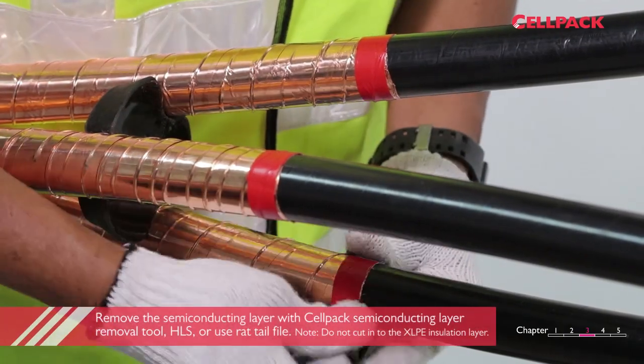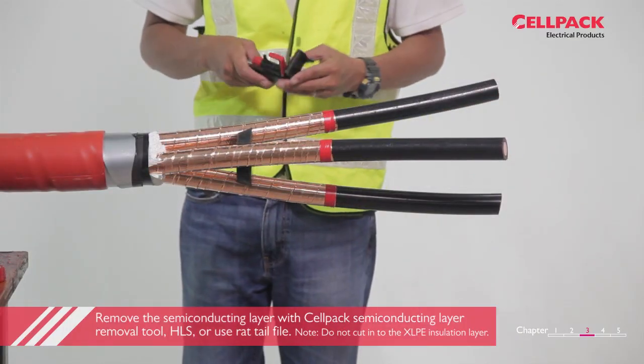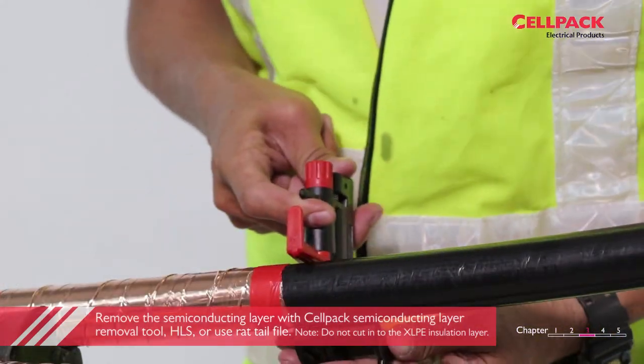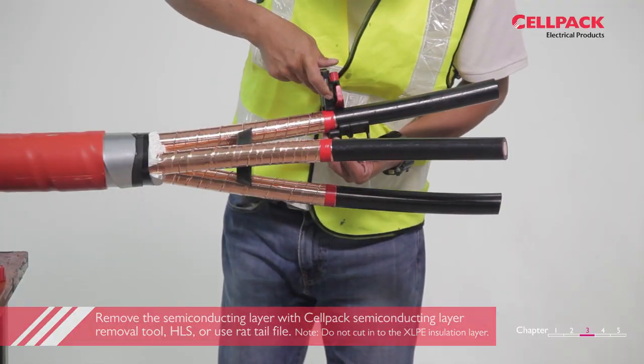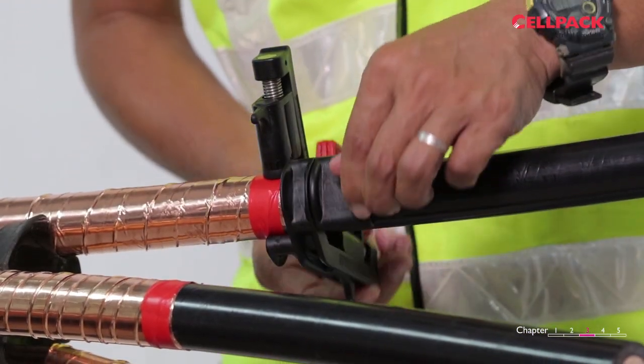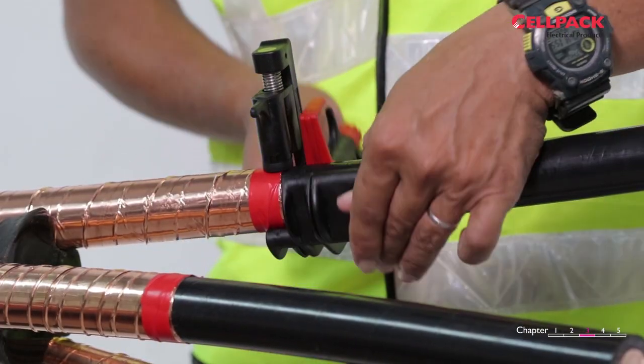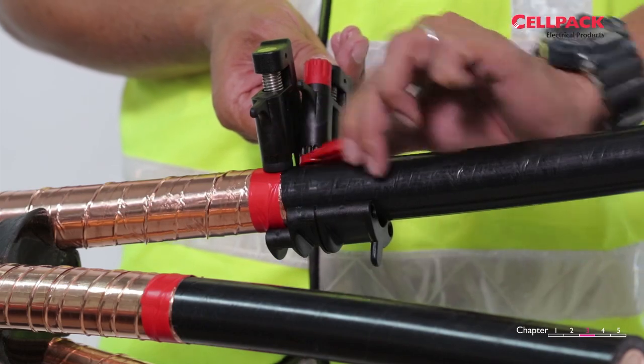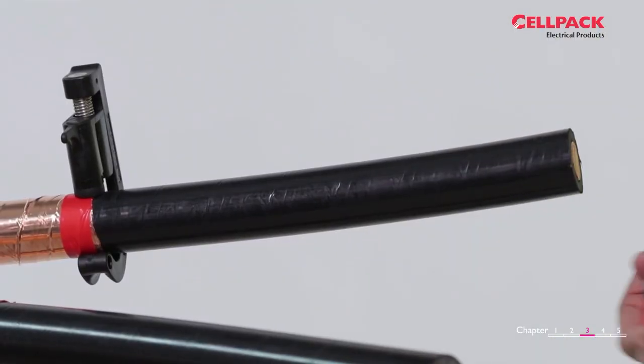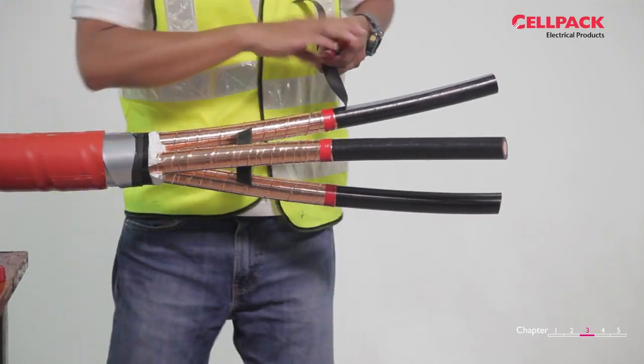Now we are going to remove the semi-conductive layer. There are two methods that can be used. The first method is by using Cellpack Semiconducting Layer Removal Tool HLS. There are two parts of the tool: the red part and the black part. Put the blade of the red part of the tool 20mm from the copper tape screen cut edge. Put the black part of the tool beside the red part. Set the direction of the red part of the tool and make a full round cut first, followed by changing direction to give three or four longitudinal cuts. Pull out the semi-conductive layer.